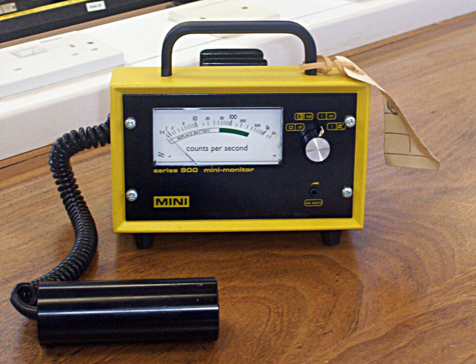A skilled operator can use varying distance from a radiation source to differentiate between alpha and high-energy beta particles. The pancake Geiger-Müller tube is a variant of the end-window probe, designed with a larger detection area to make checking quicker. However, the pressure of the atmosphere against the low pressure of the fill gas limits the window size. Some beta particles can also be detected by a thin-walled, windowless Geiger-Müller tube, which has no end-window but allows high-energy beta particles to pass through the tube walls.